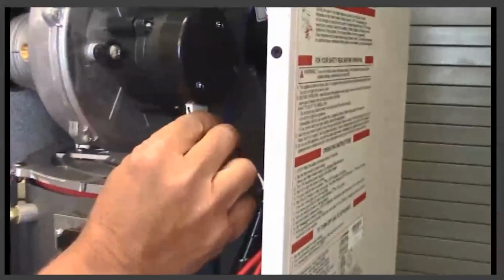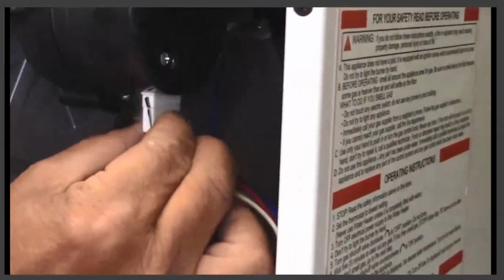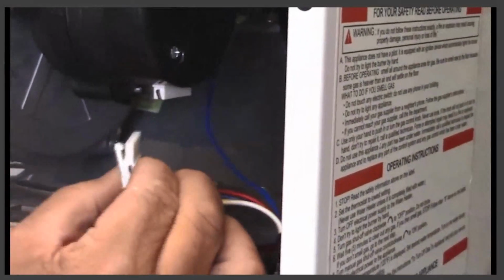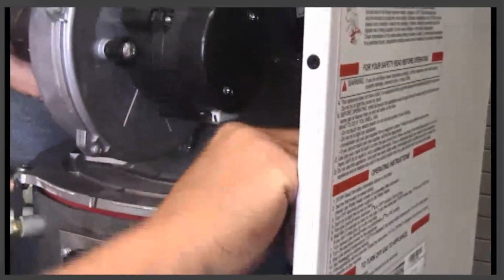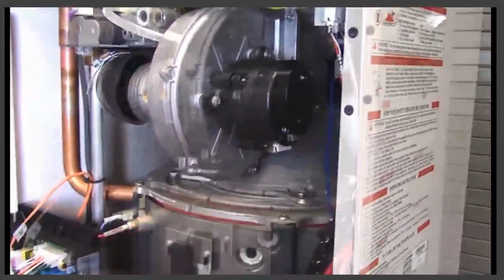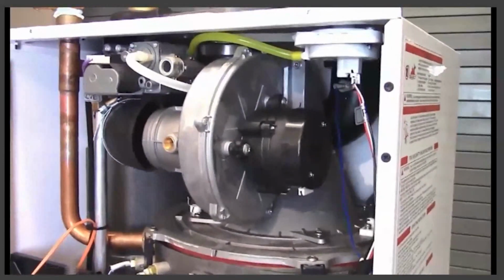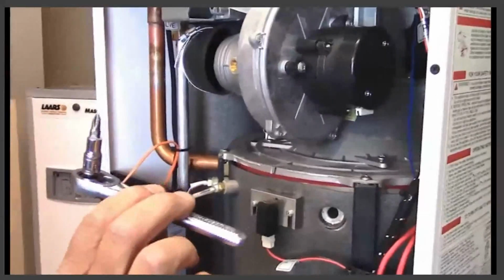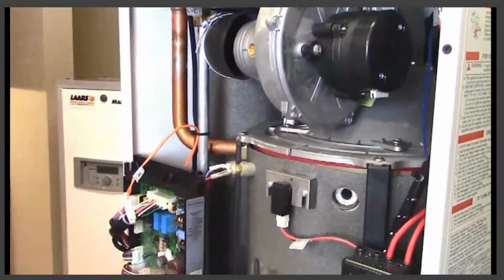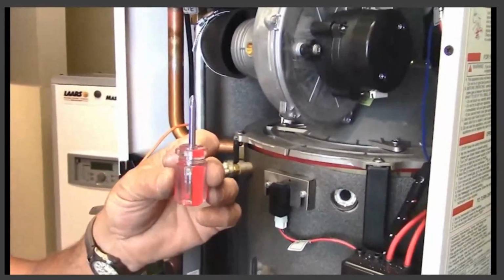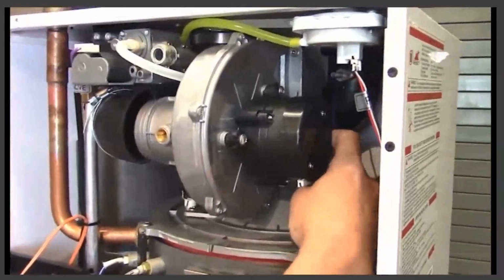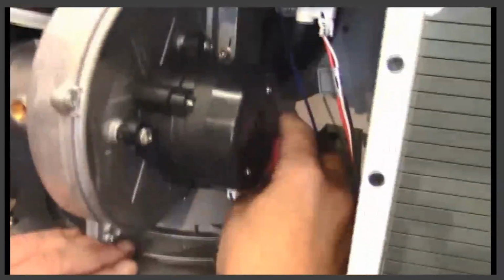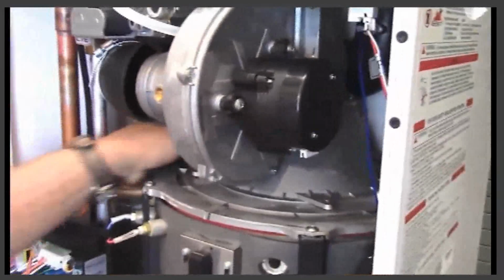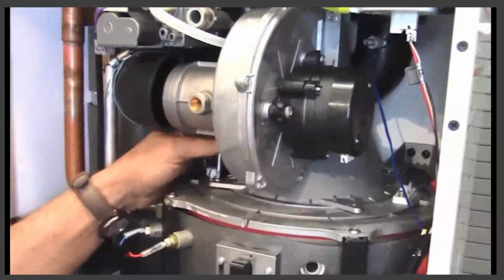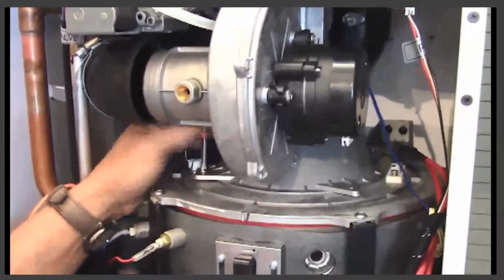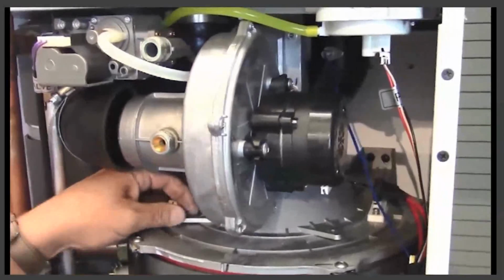Removal of the electrical connector for the blower motor: also a lock, squeeze, pull down. You can see the lock there on that Molex connector. And you can move that wiring out of your way. One of 2 tools is necessary. One can be a small ratchet. What you're seeing there is a 1/4 inch ratchet with a Phillips head adapter on it, or a very small stubby Phillips head screwdriver. Loosen the 4 screws that hold the blower plate down onto the boiler itself, 2 screws in the front, 2 screws in the back. They can be accessed either with that Phillips head screwdriver or the Phillips head attachment on the ratchet.